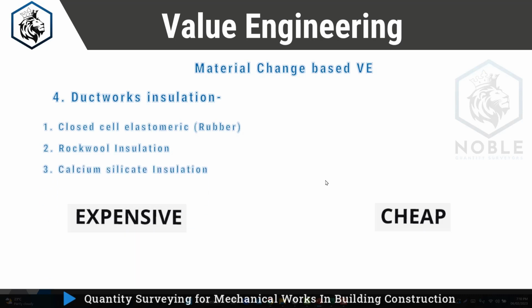The next is calcium silicate insulation, which is the most expensive insulation in HVAC works, costing around 60 to 70 dirhams per square meter. Your closed cell rubber insulation costs around 33 to 40 dirhams per square meter. And rockwool insulation comes around 26 to 35 dirhams, based on the thickness of the insulation.